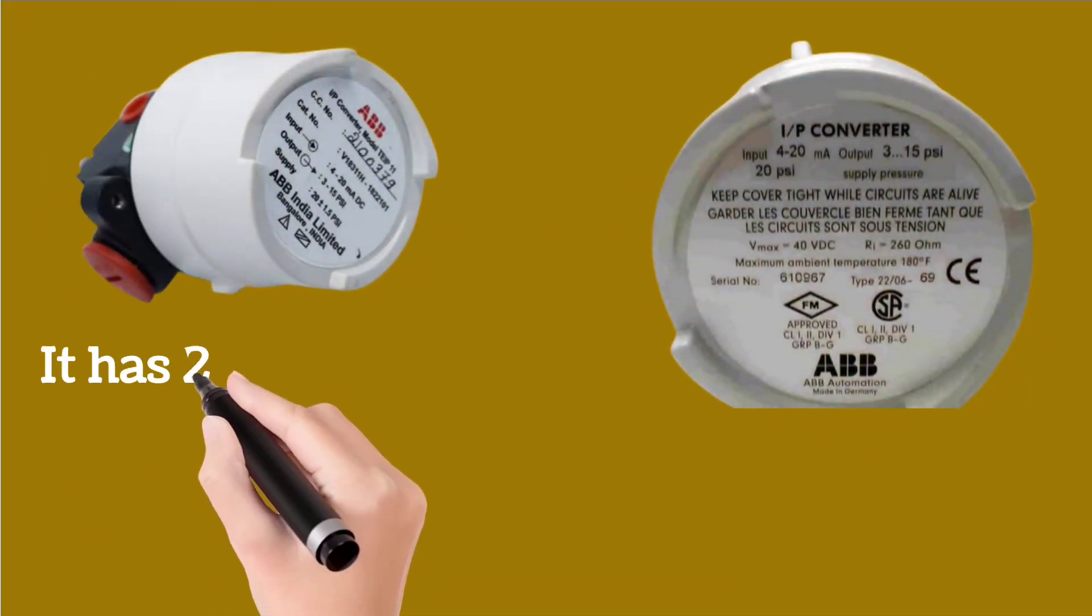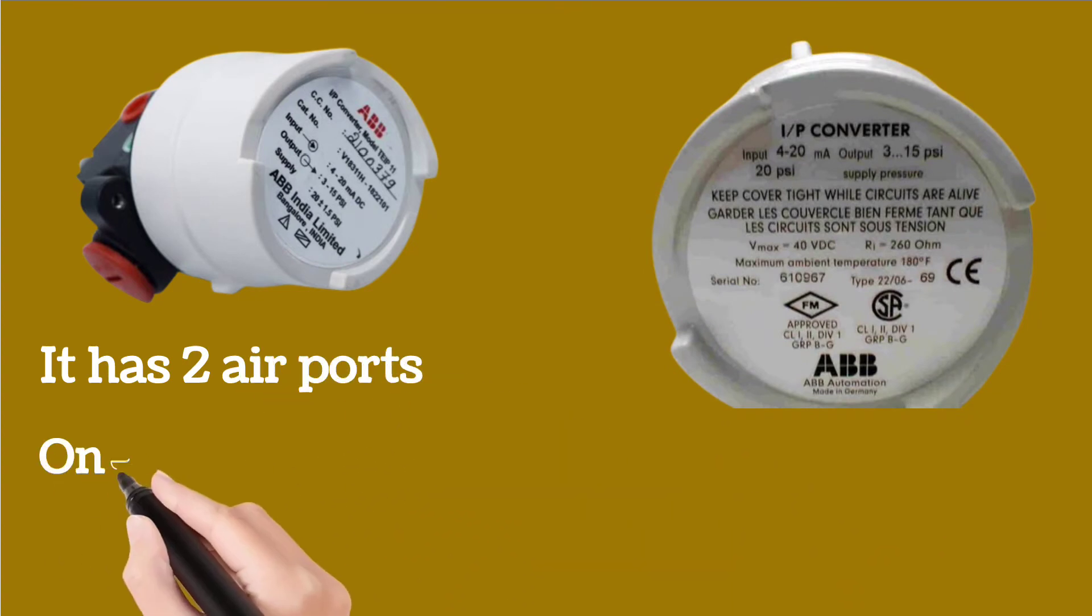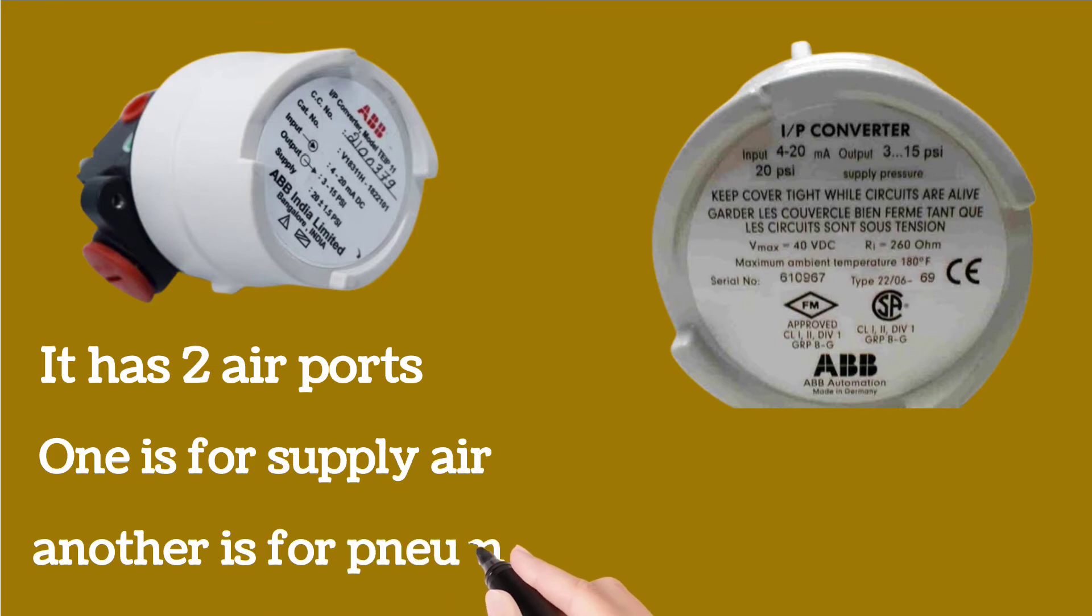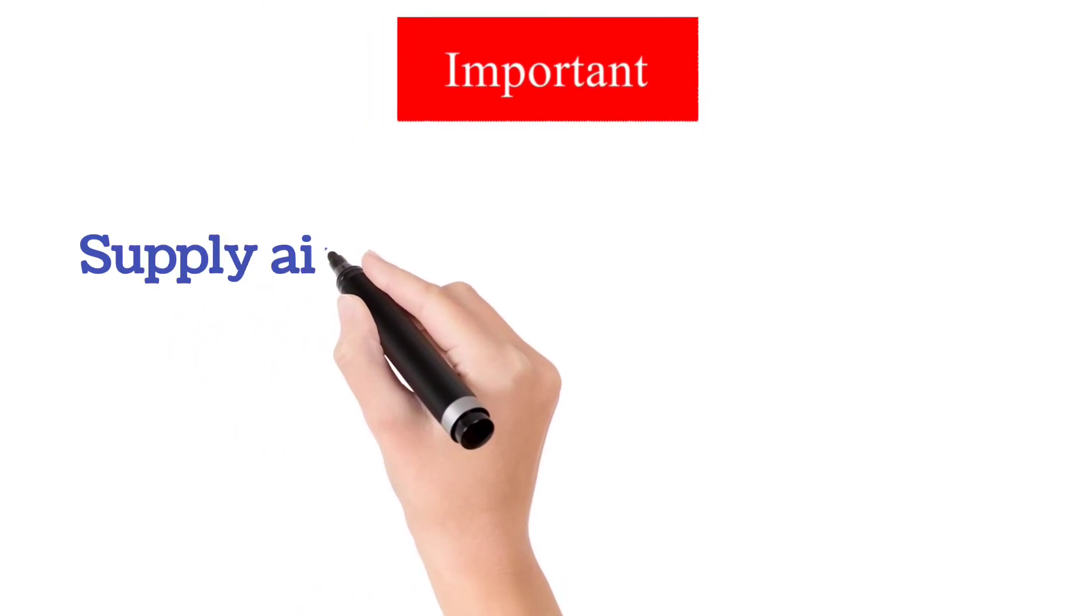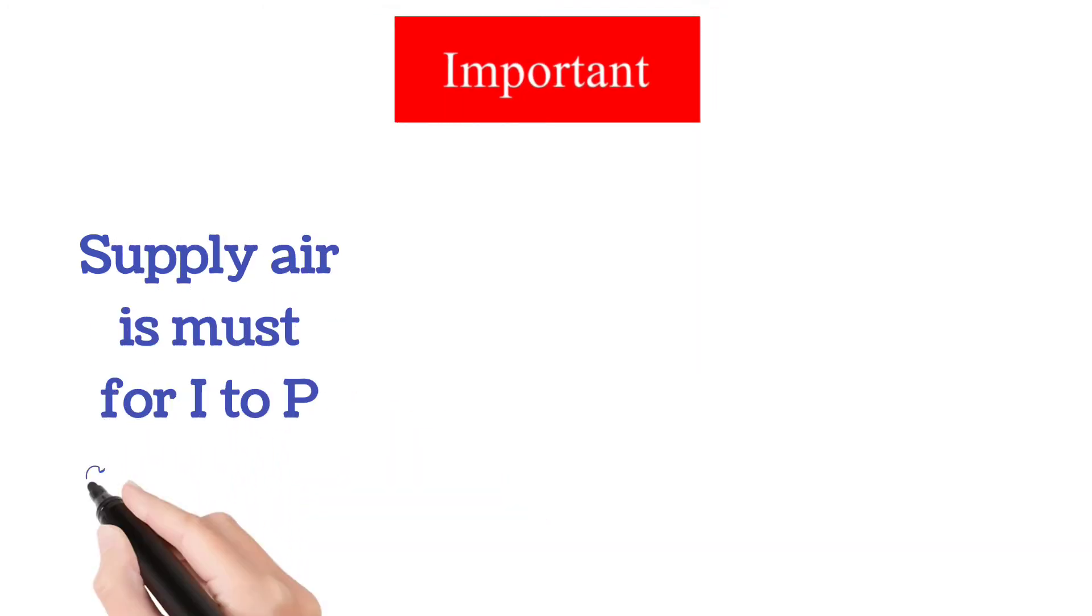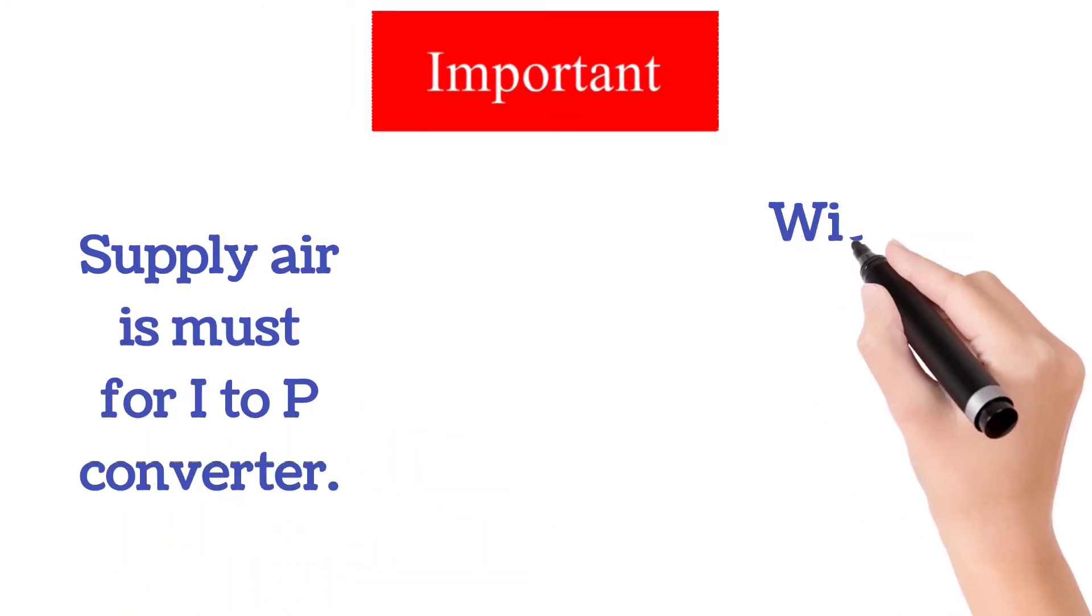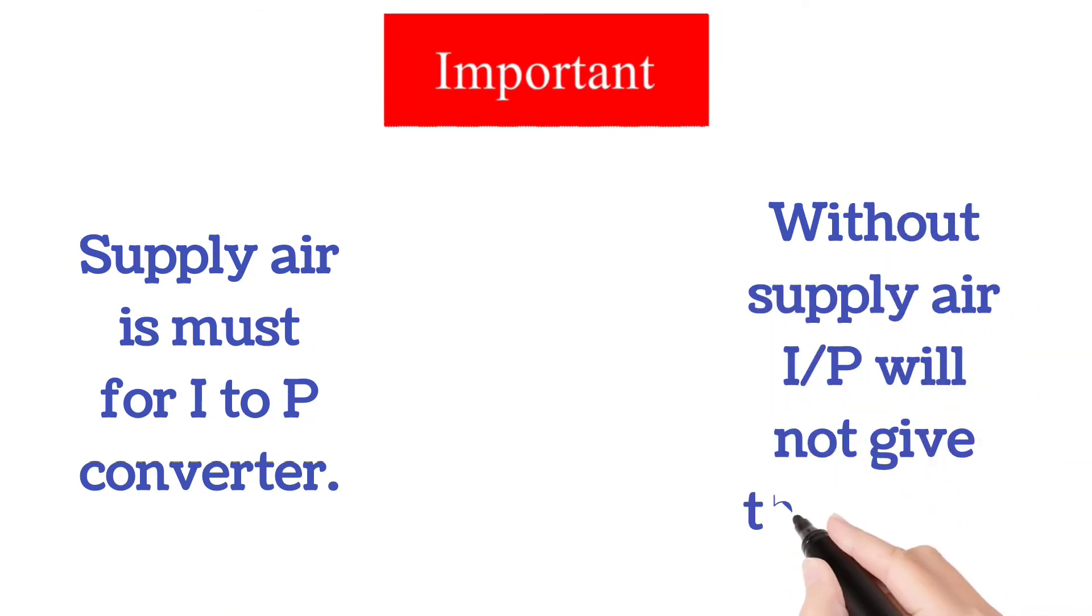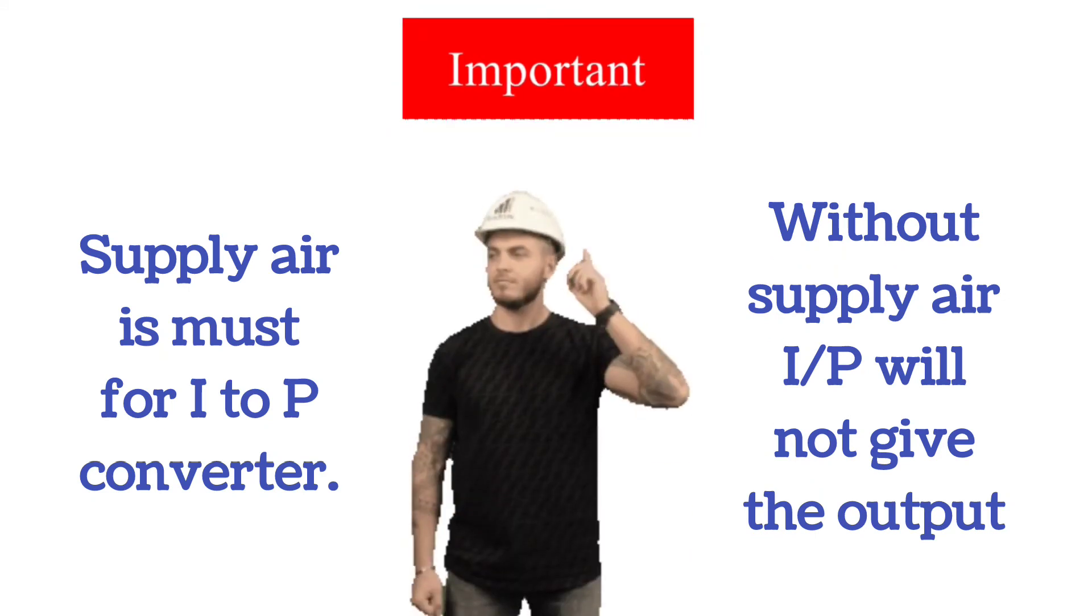I to P converter has two air ports. One is for supply air and another is for pneumatic valve positioner. Here one point is important to note that supply air is a must for I to P converter. And without air supply, it will not give output or it will not operate a control valve.